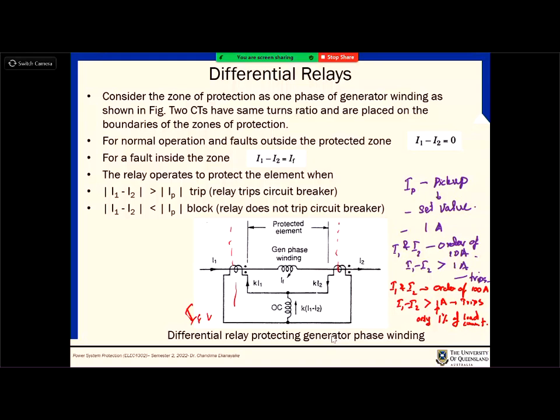If there is a fault, as an example, if this fault is here, then there will be a current difference, because you can clearly see that a certain part of the current is going to the ground. Therefore I1 coming into this protected zone is not equal to I2, right? So fault current plus I2 will be equal to I1, something like that.